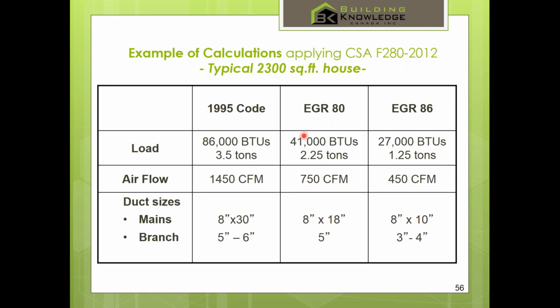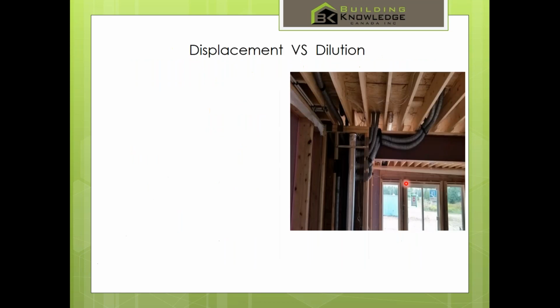As we move from BTUs to lower heat loads, you move from higher CFMs to lower CFMs, which means you have to have smaller ductwork and you better seal the life out of this ductwork. So if we can get anything across today, it's that low load homes will require the ability to move lower CFM more often, if not continuously, in homes if you're using air delivery comfort systems. This is why we have to change our language.